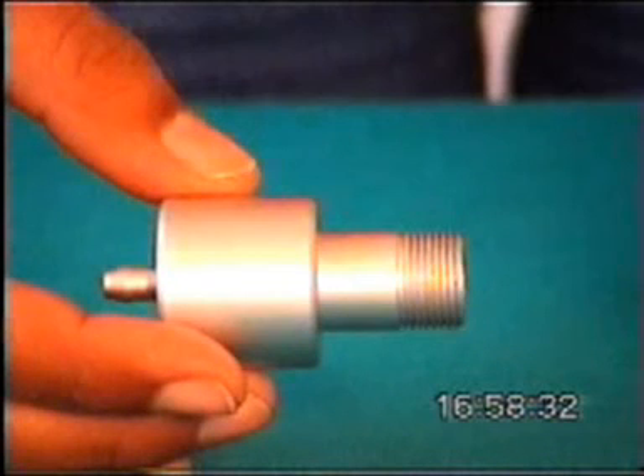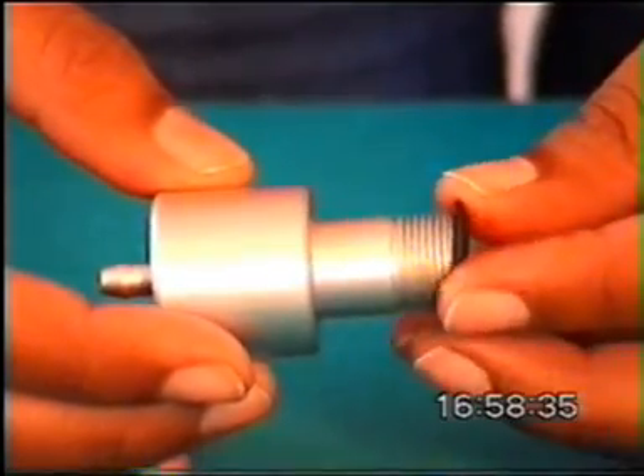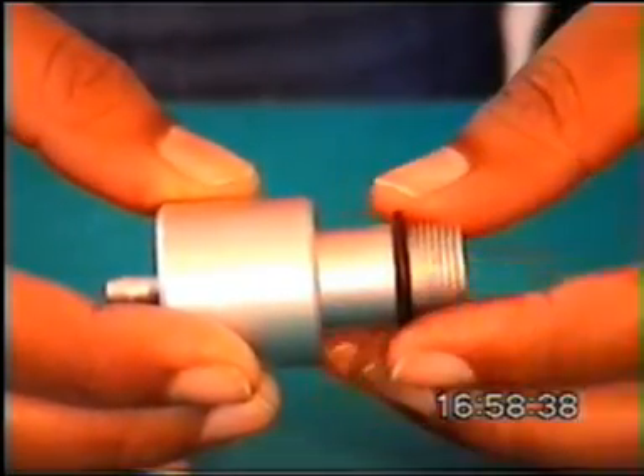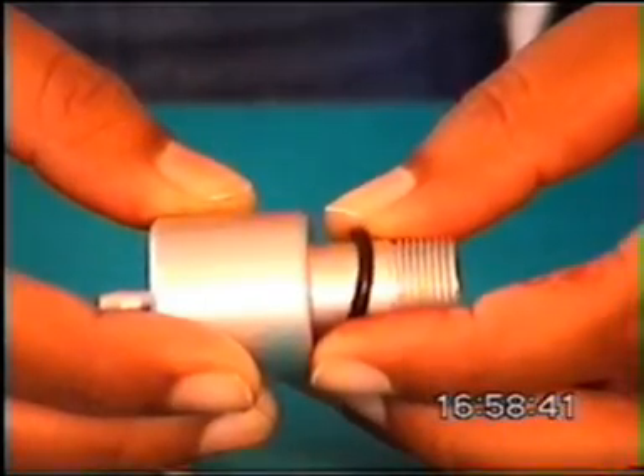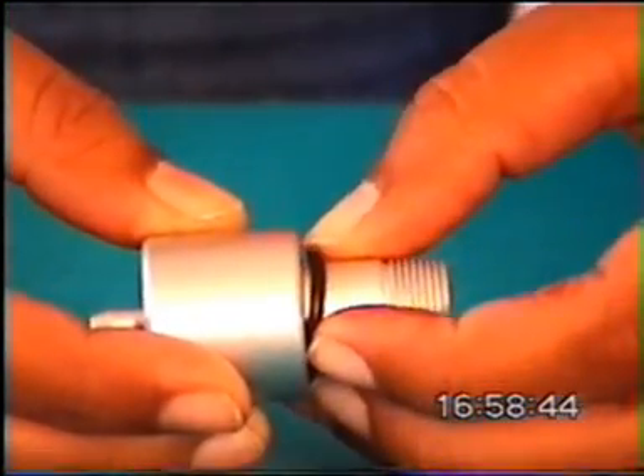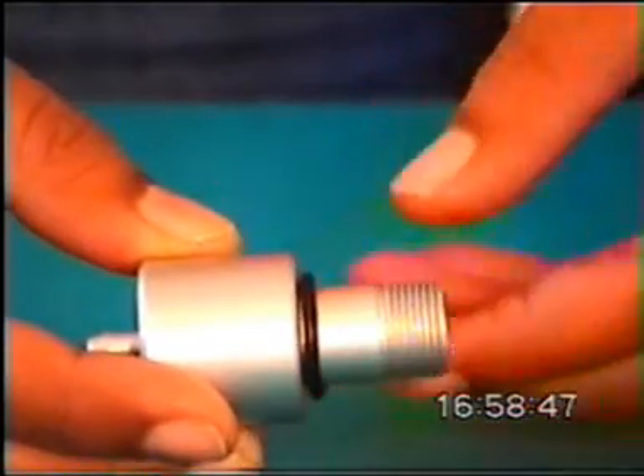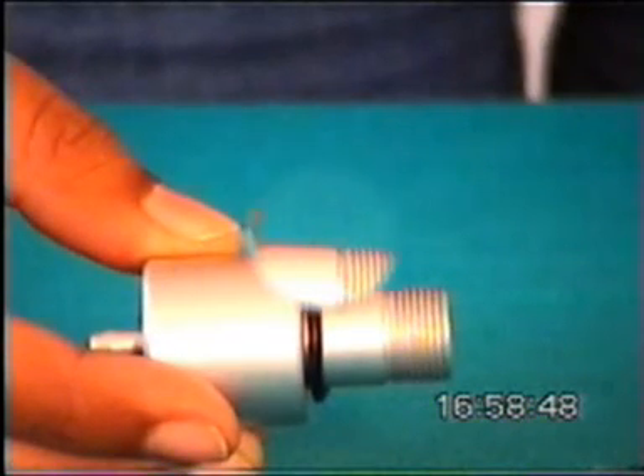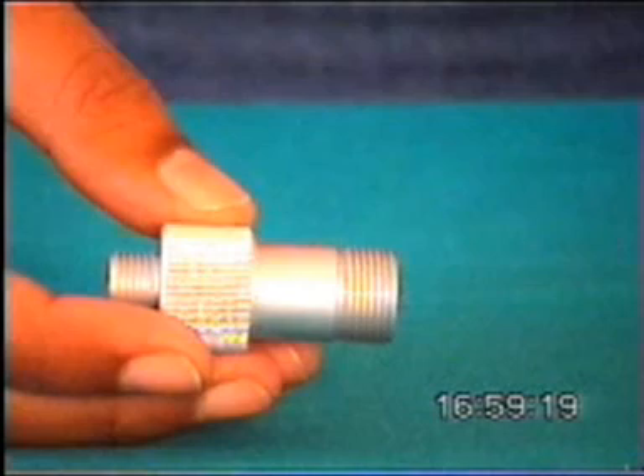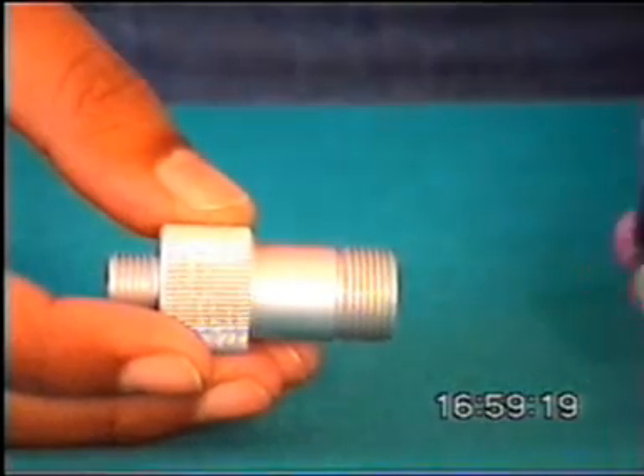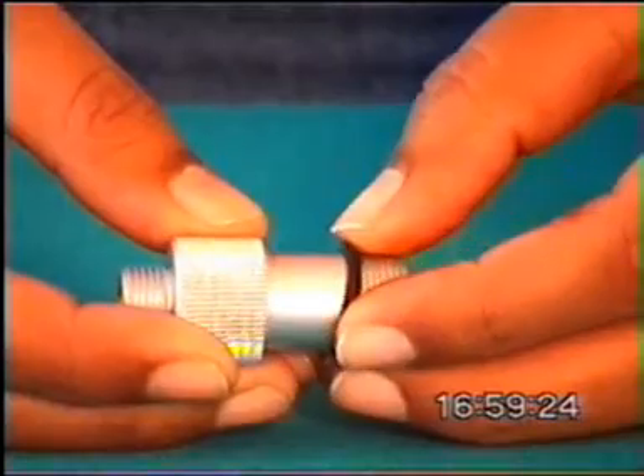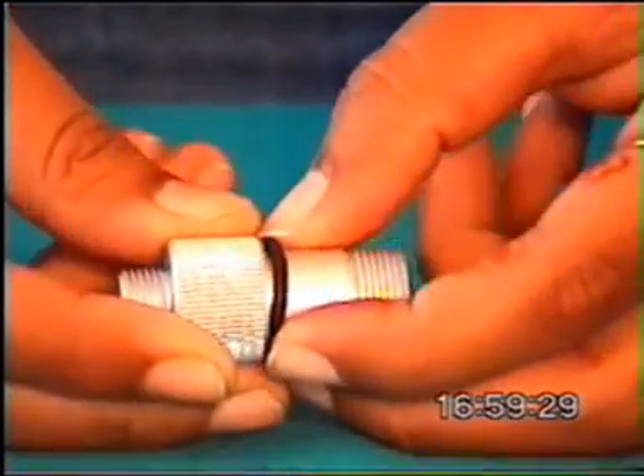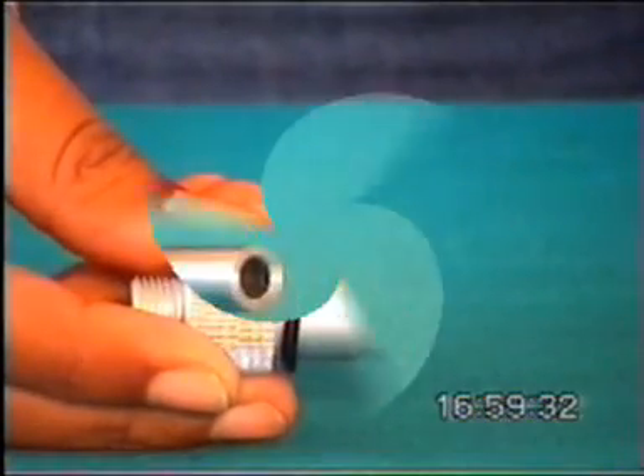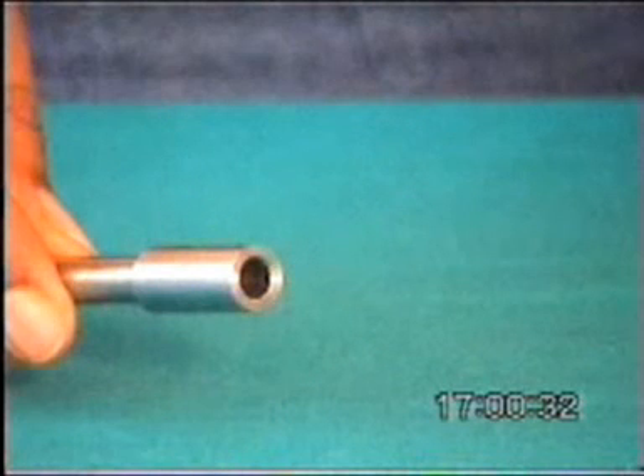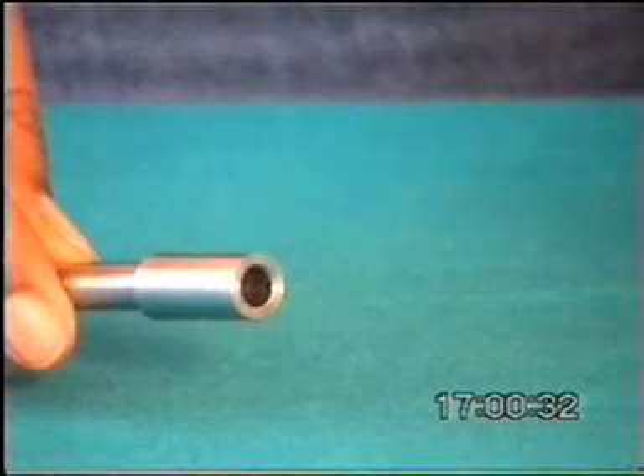The LITHOSPLIT Super Handpiece is extremely lightweight and very convenient to handle during operation. It can be assembled practically in just a few minutes. Let us see how. First, a rubber O-ring is fitted onto the inlet. A rubber O-ring is fitted onto the probe cover. This is the front end of the cylinder. A piston cannot go in from this end.